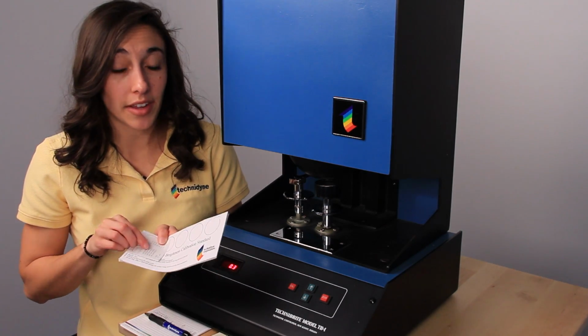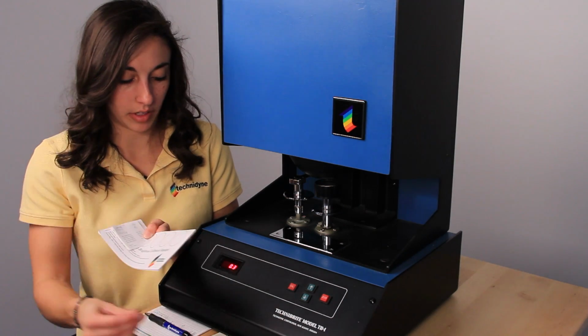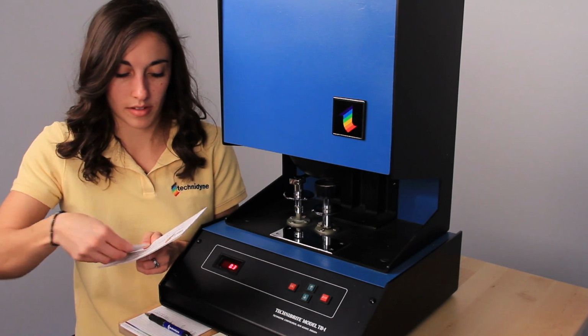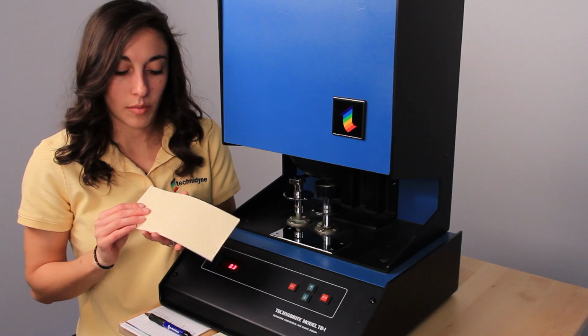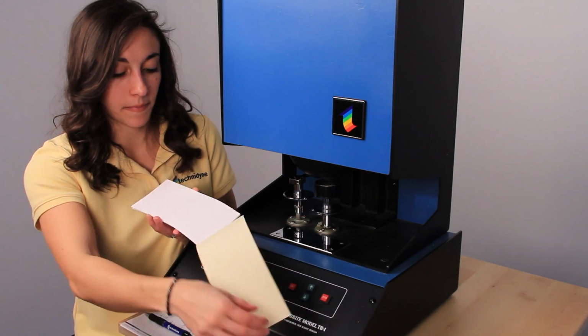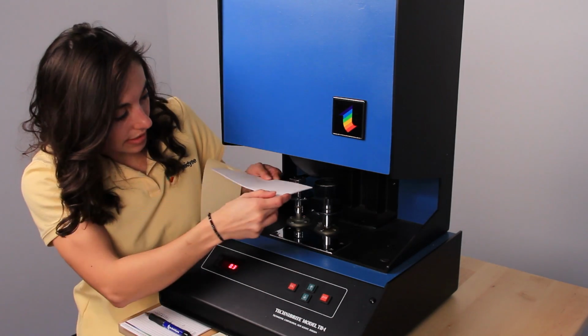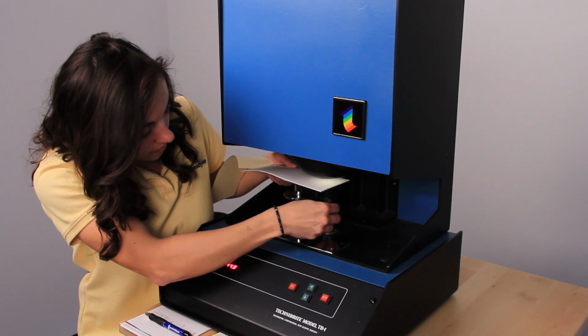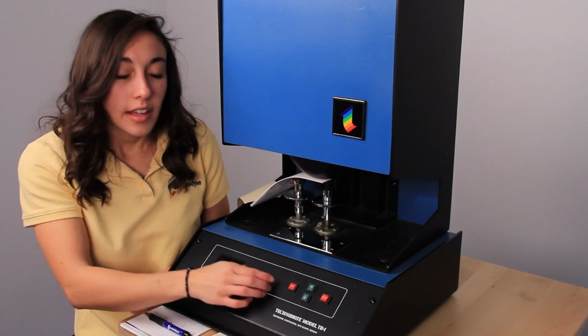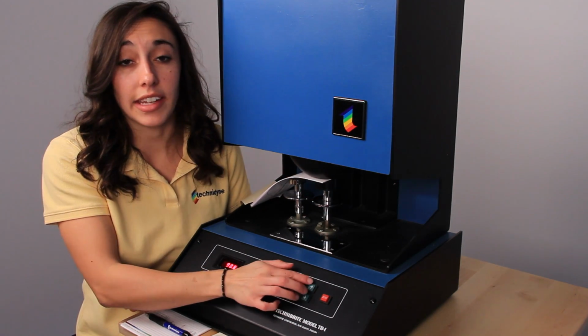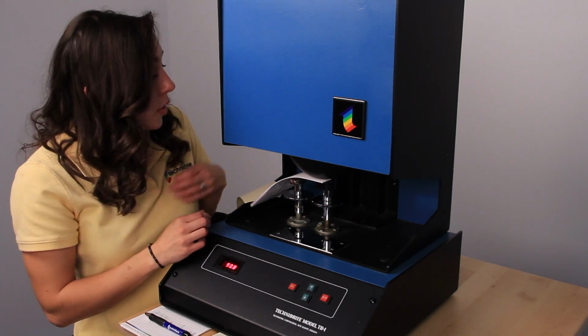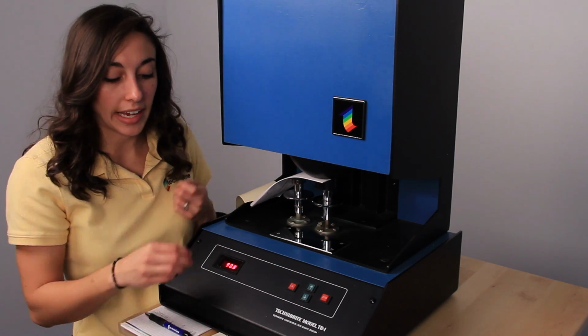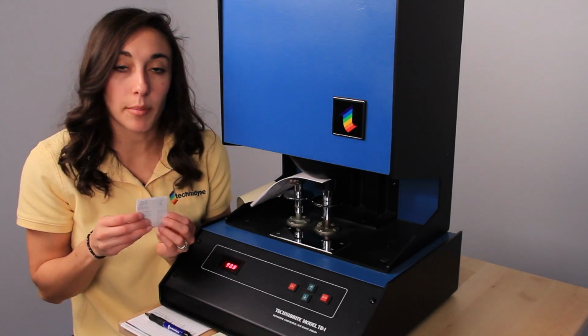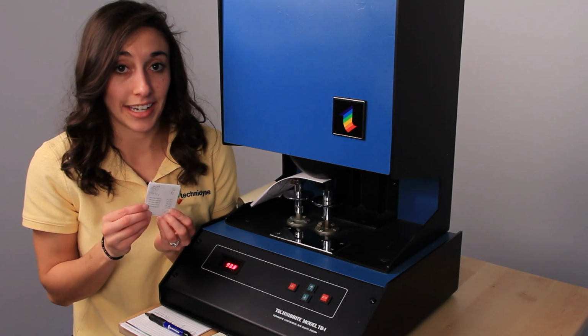So like we did with the 70 standard, we'll take the paper clip off, and we'll fold this back cover sheet back, and we'll load it right to the edge. Instead of the Calibrate buttons and the arrow keys, this time we're going to use a knob by the UV light in order to match the display number with the number on the 90 standard printouts.